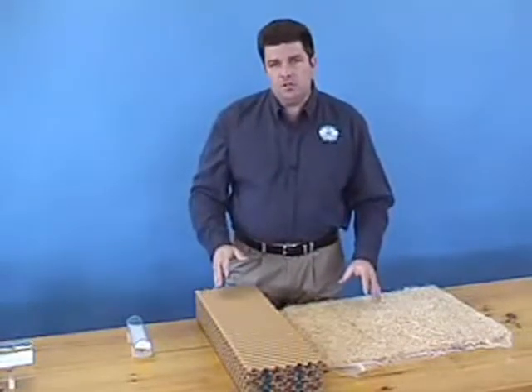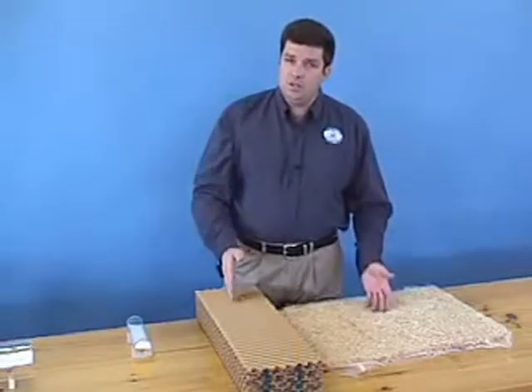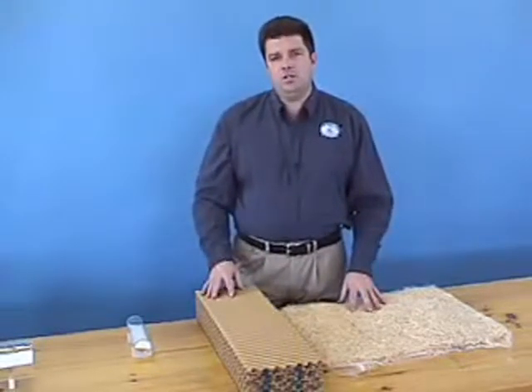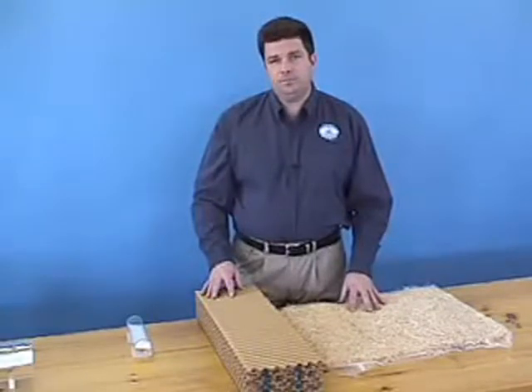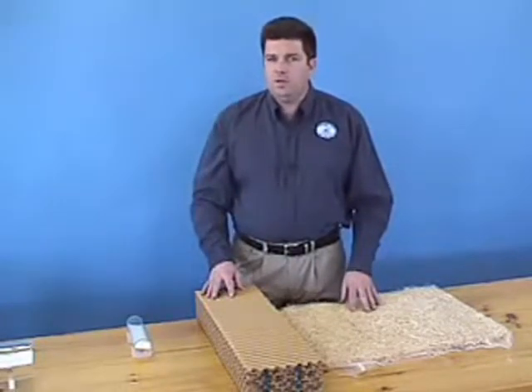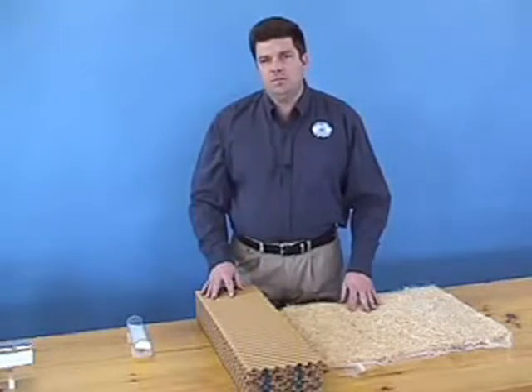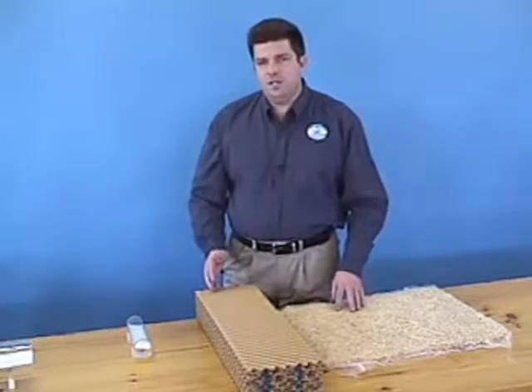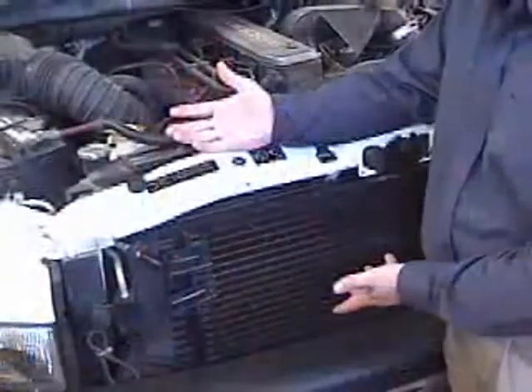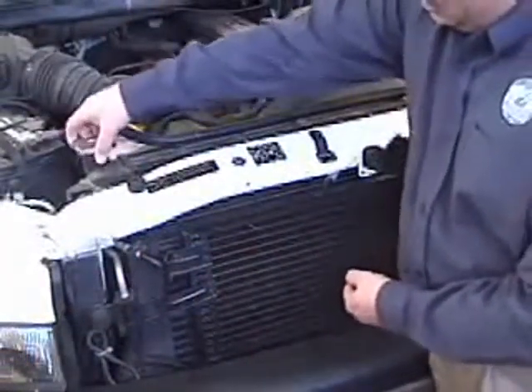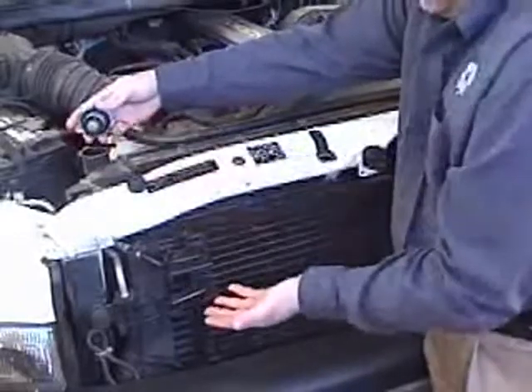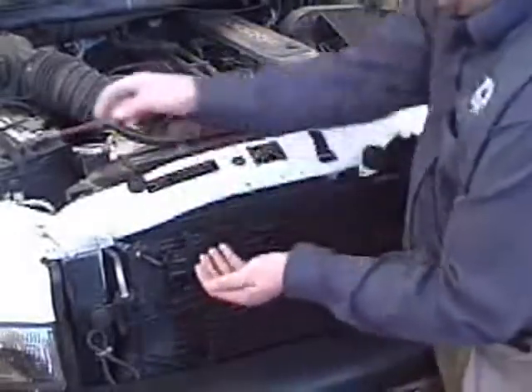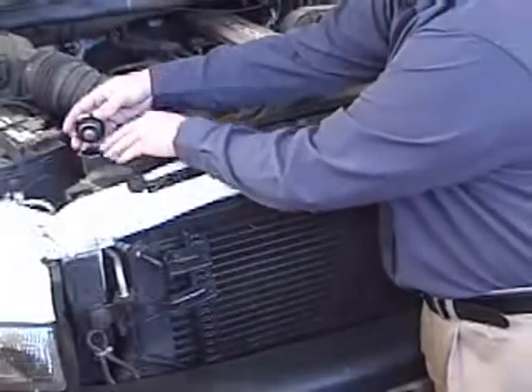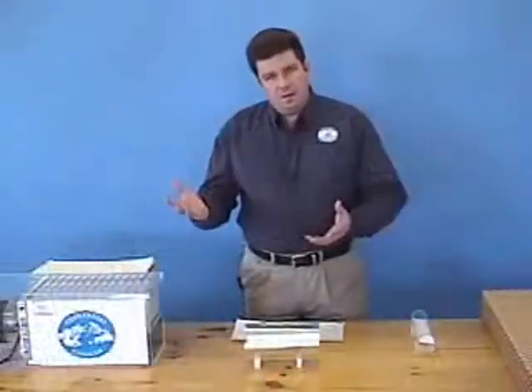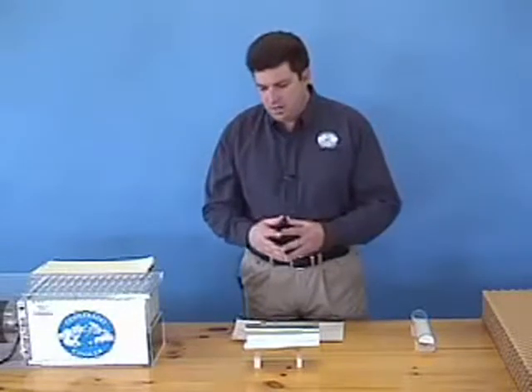Indirect evaporative coolers use the principles of evaporation, but it does not add any moisture to the air entering the building. An indirect evaporative cooler utilizes a heat exchanger. A common example of a heat exchanger is the radiator in a car. The hot liquid in your car's radiator transfers heat to the air outside without the air from the outside getting in, or the hot liquid from the inside getting out. The same heat exchange principle is true for an indirect evaporative cooler.